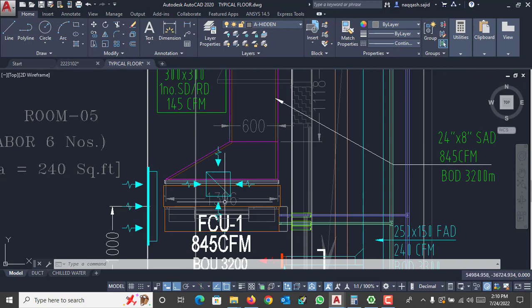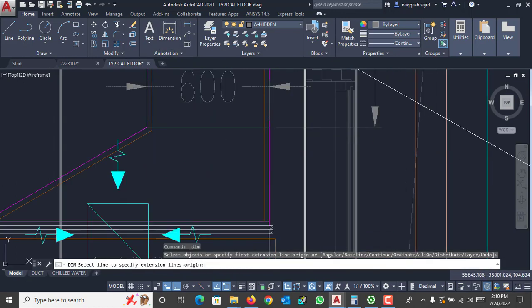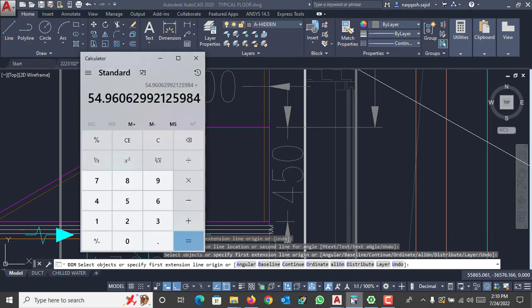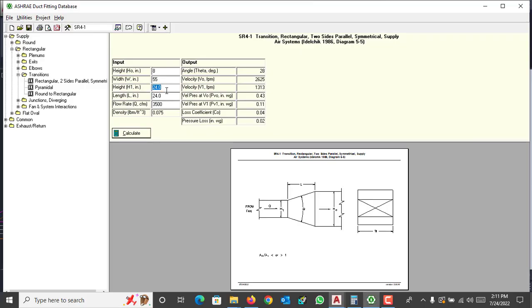The duct width is 55 inches and the height is 8 inches. I also need the length of this transition, which is 450 mm — approximately 17.7 inches — so I enter 17.7 inches in the length field. The height is the same for both sides. The CFM passing through this transition is 845 CFM. Press calculate — there is not much pressure loss in this duct. Add it to your project for later.